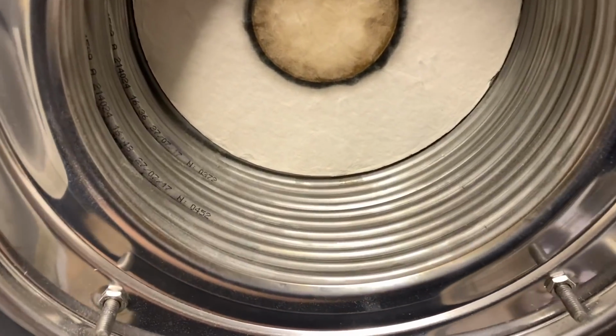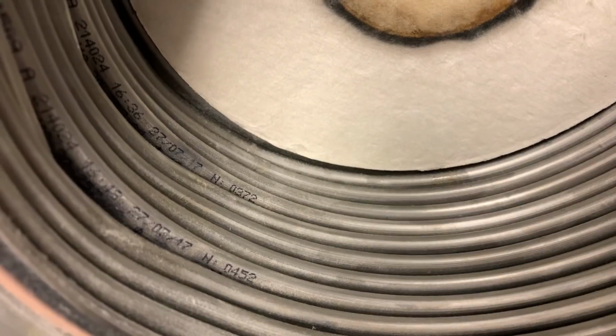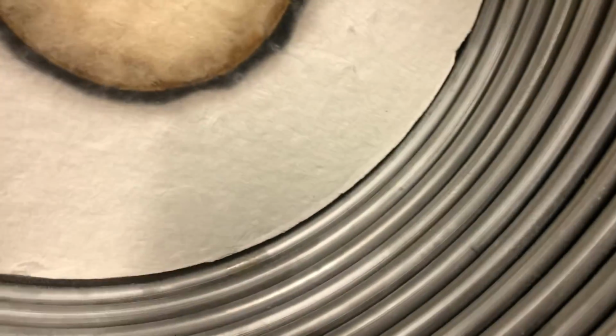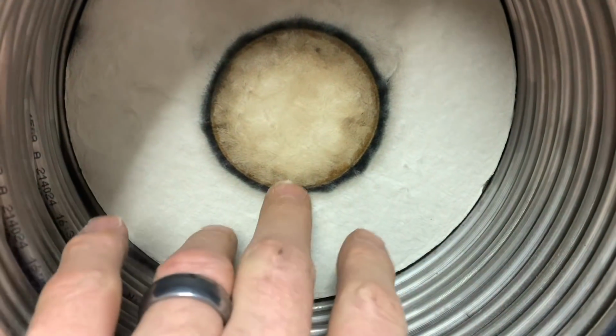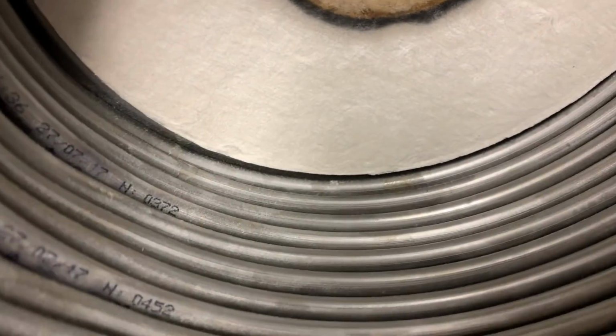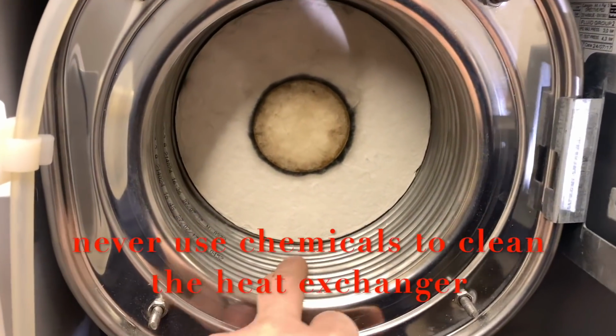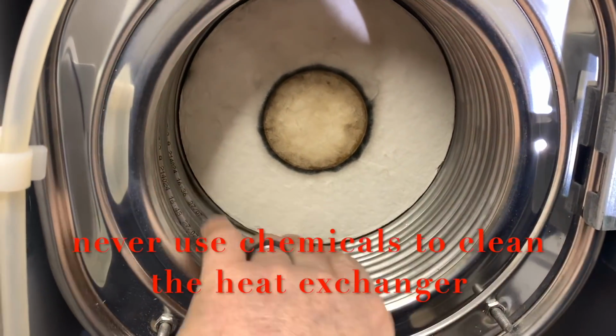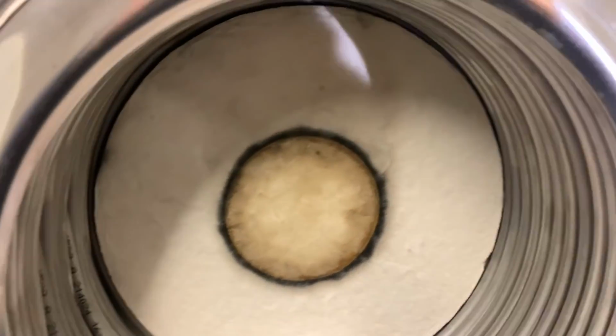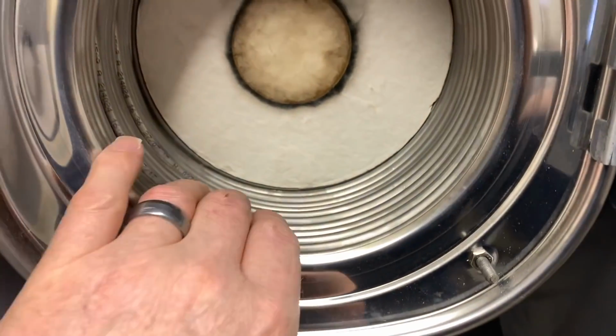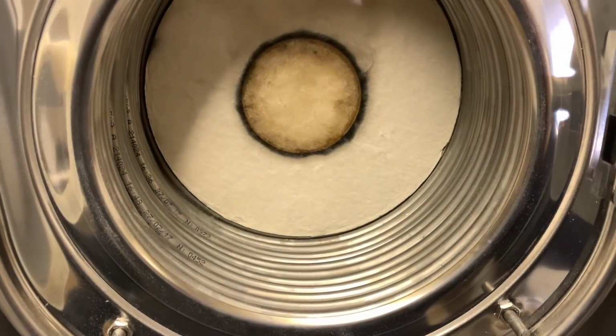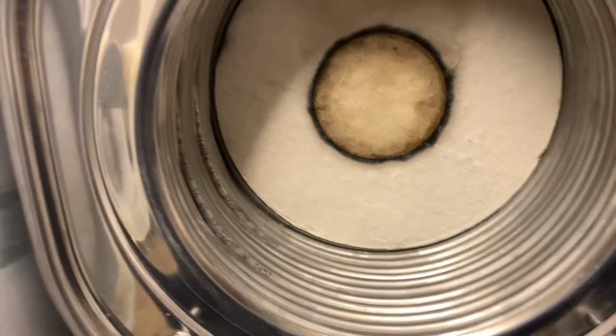So now we can see the heat exchanger itself, and you can see it's the older two coil pass system rather than the one which is like the 28mm squashed. So this has two 10mm coils, so these are 10mm the size of them. Again, we've got a heat shield at the back, and again, if this is damaged, then it needs to be replaced. So cleaning them, again, when we come to clean them, you can't use anything abrasive in there, so anything metal. So clean off the debris, but they are incredibly easy to clean, and they do last quite a long time. They are very robust, a lot more robust than the aluminium heat exchangers. So pretty standard heat exchanger, you've seen them all before.